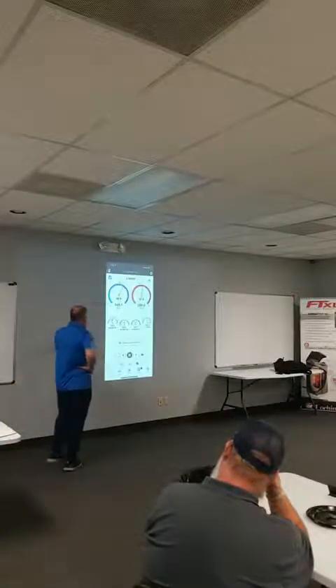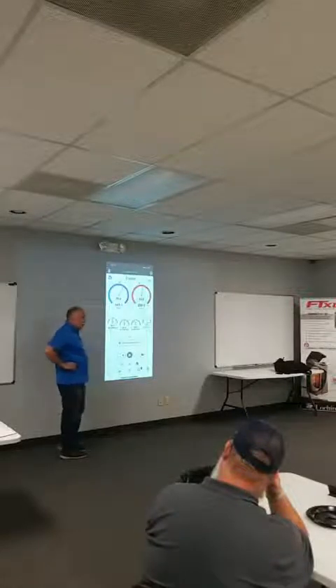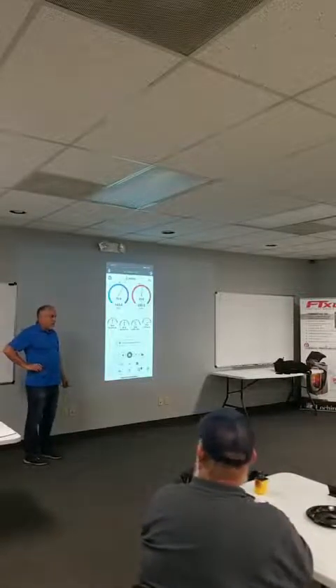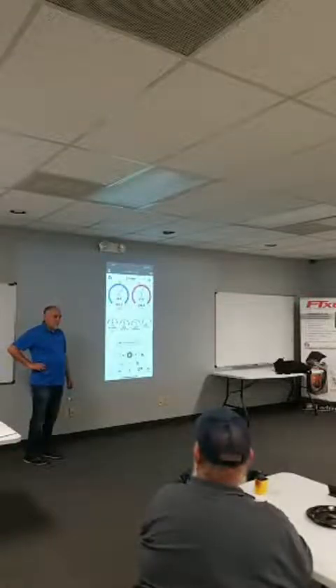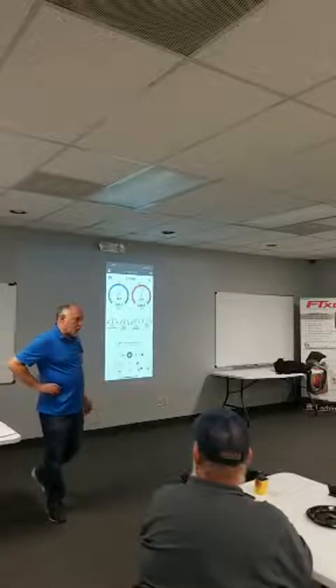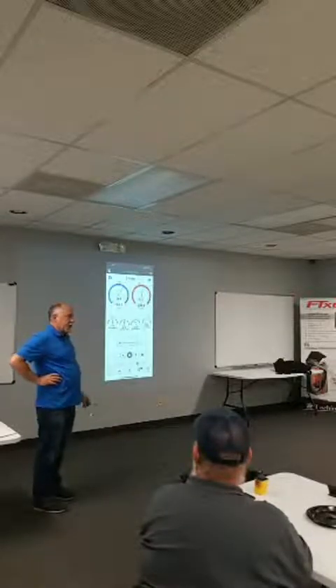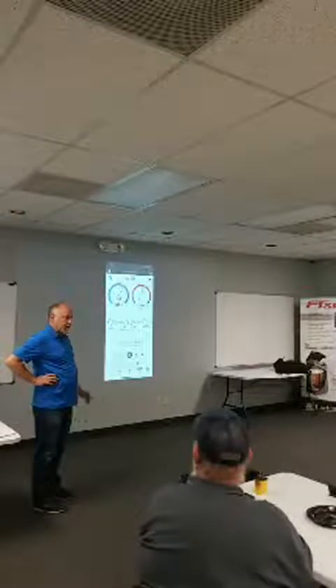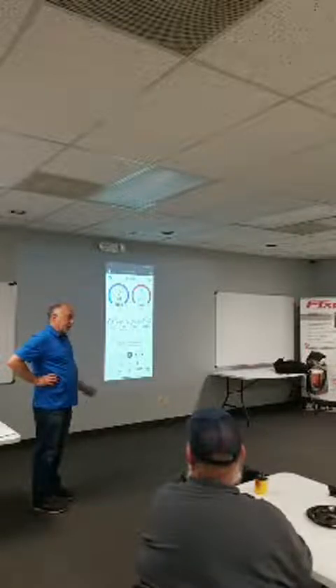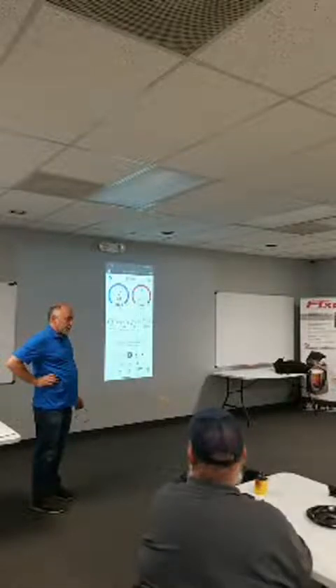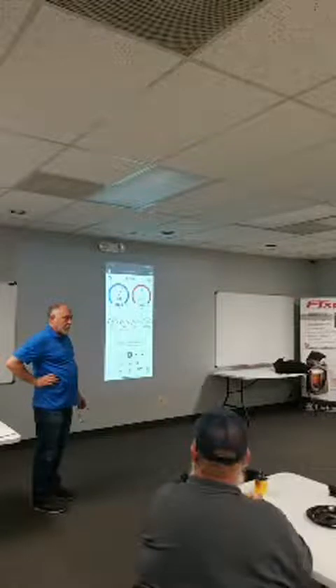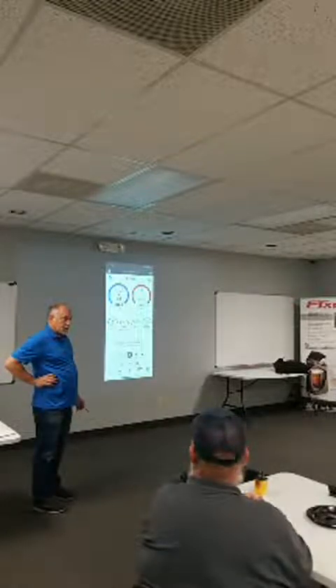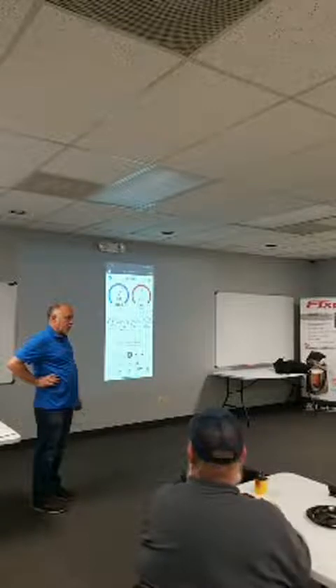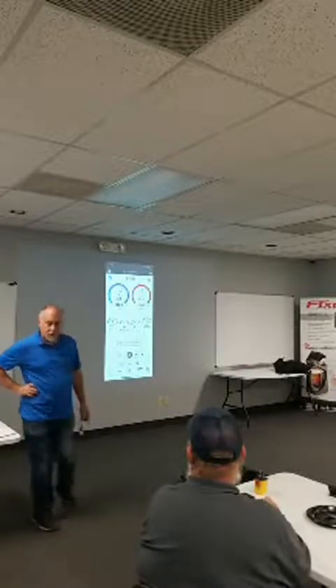Now this machine's coming down here. We got a 76-degree return air. Does return air temperature have a range? Sure, it should be around a design of 75 and 50. If I told you the design temperature difference is 35 degrees at the evaporator coil, if it's 70 minus 35, what's that? 35. If it's 68 minus 35, what is it? Too low. 32. What happens at 32 degrees? Water freezes on the coil. You can see it too on here, you can see it just drops like a rock. And what will happen if water freezes on the coil? Airflow goes down, and you're going to have other issues, right?